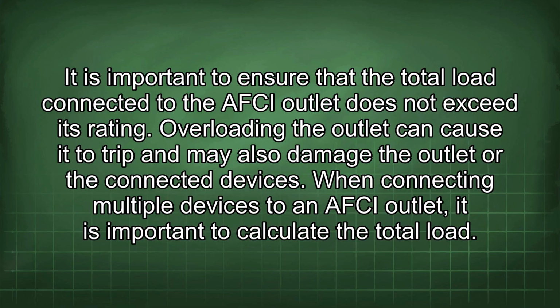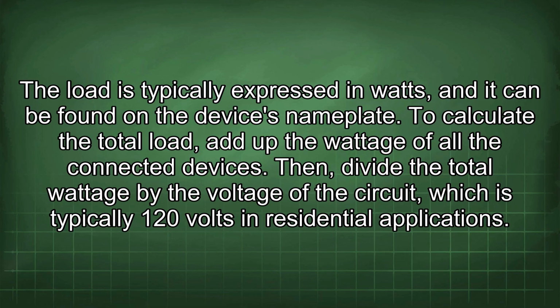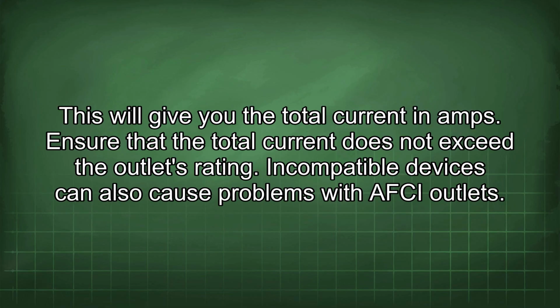When connecting multiple devices to an AFCI outlet, it is important to calculate the total load. A load is typically expressed in watts, and it can be found on the device's nameplate. To calculate the total load, add up the wattage of all the connected devices. Then divide the total wattage by the voltage of the circuit, which is typically 120 volts in residential applications. This will give you the total current in amps. Ensure that the total current does not exceed the outlet's rating.